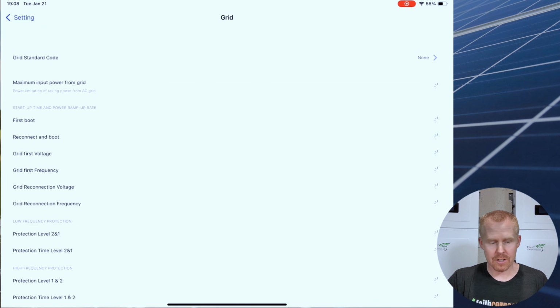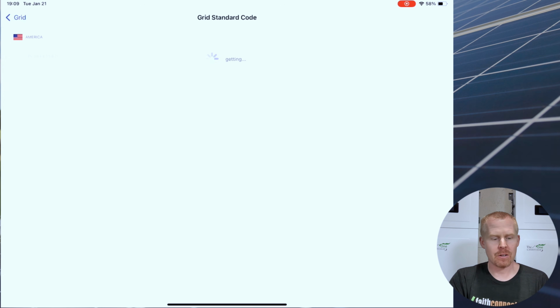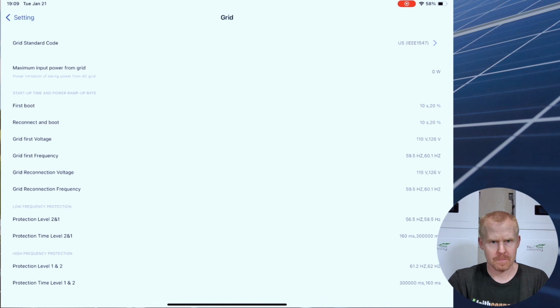Looking at the grid sections, the grid standard code, there's only one option, the US IEEE 1547. Maximum input power from the grid. This is the maximum power including the pass through to loads, as well as battery charging. It can go from 0 to 24,000 watts.